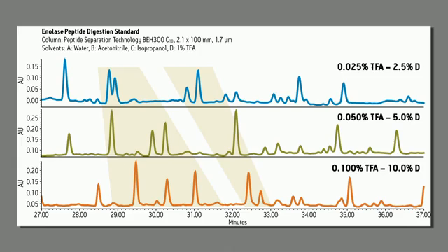Instead of having to make multiple bottles of solvent to do our separation development, we just form different compositions by programming different percentages from the software. We can change TFA concentration, or we can get a different selectivity by replacing some or all of the acetonitrile with isopropanol.